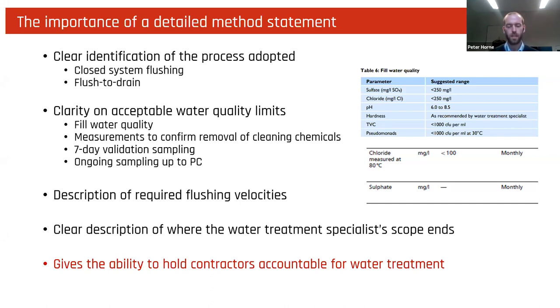So that CP1 2020 at the bottom of less than 100, we would always opt to go for that over a 250 milligram per litre as stated in BG29. Again, we just want a clear process outlined in our method statement. And another key point just at the bottom there is a clear description of where the water treatment specialist scope ends. So that has to be determined between the M&E contractor and the water treatment specialist. But we want clarity from the word go so that we can maintain accountability throughout the water treatment process.